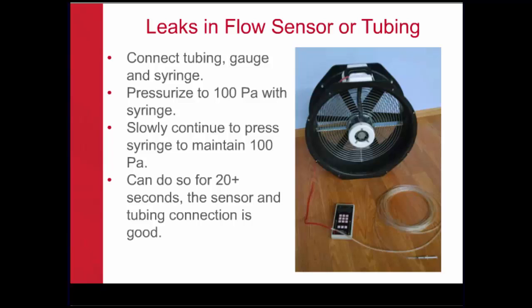Now, what this should tell you is that there are some what we would call micro leaks in all the different connections. We have a lot of different T's that go from the pressure connection in the electrical box of the fan and through to the flow sensor itself. So very small, minute leaks are okay, and you'll experience that by doing this test. If, on the other hand, you try and push the plunger down for 100 and you keep doing it and you run out of room on your plunger and you still haven't reached 10 or 15 seconds, then chances are the flow sensor has a crack in it and will need to be replaced.